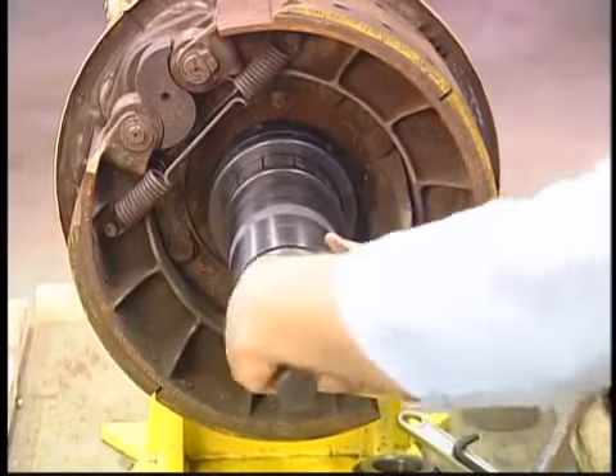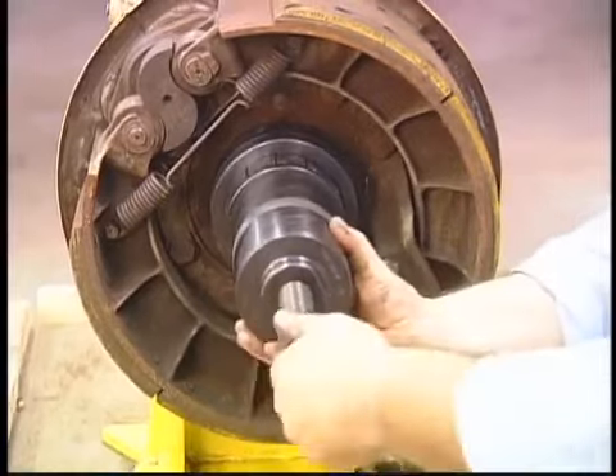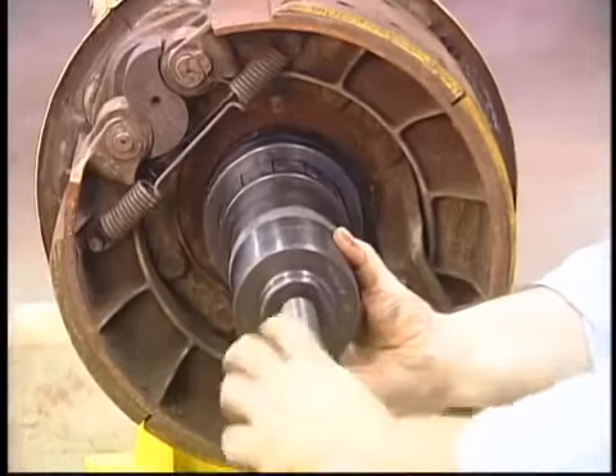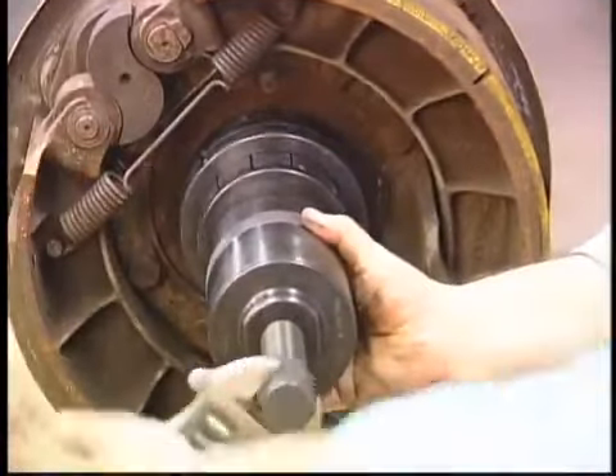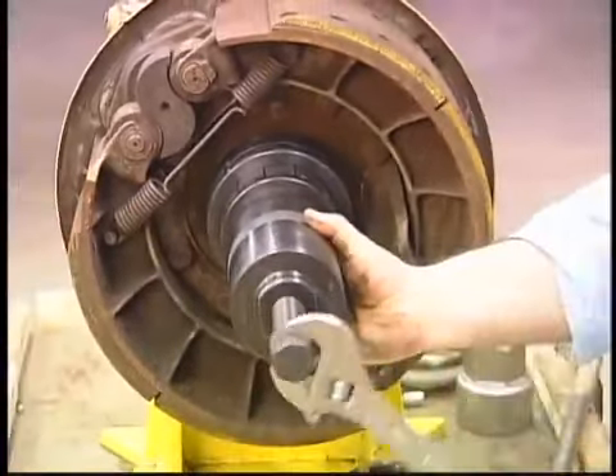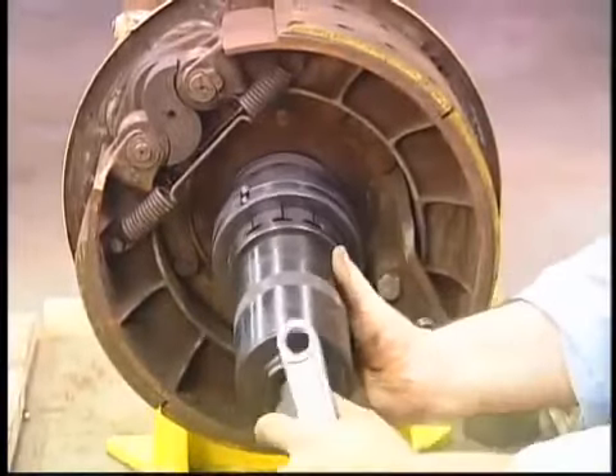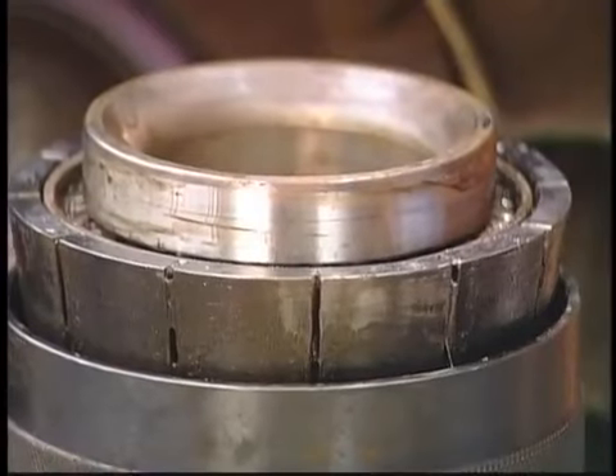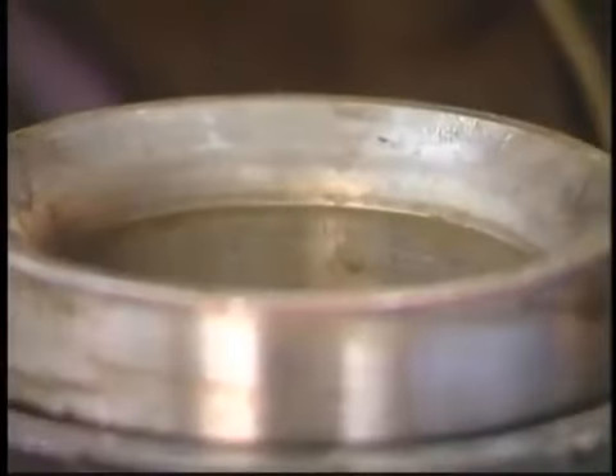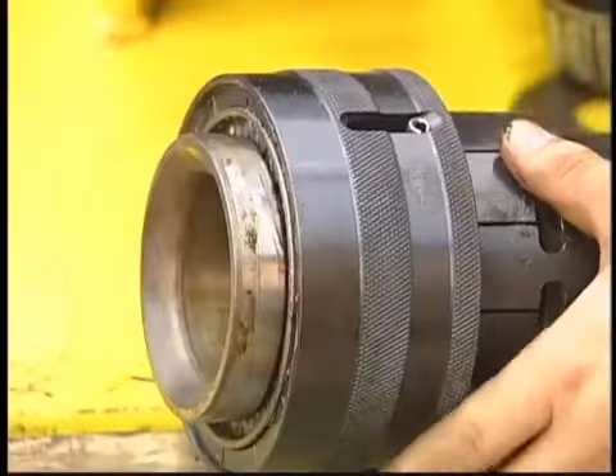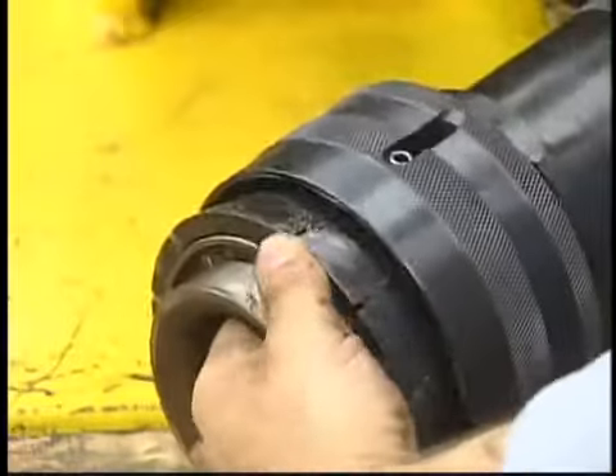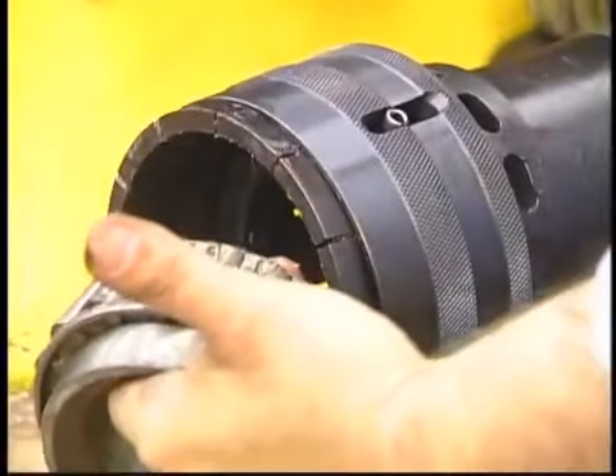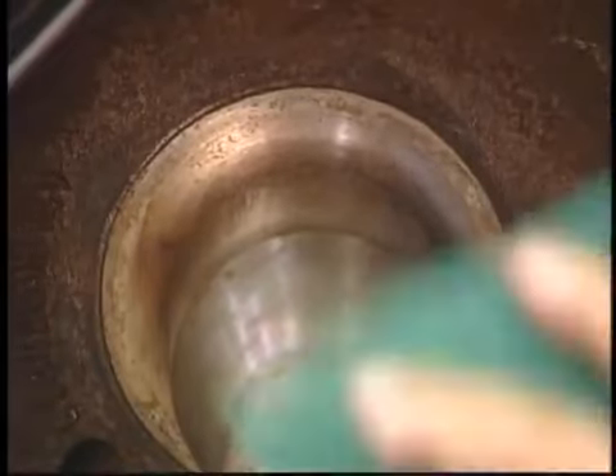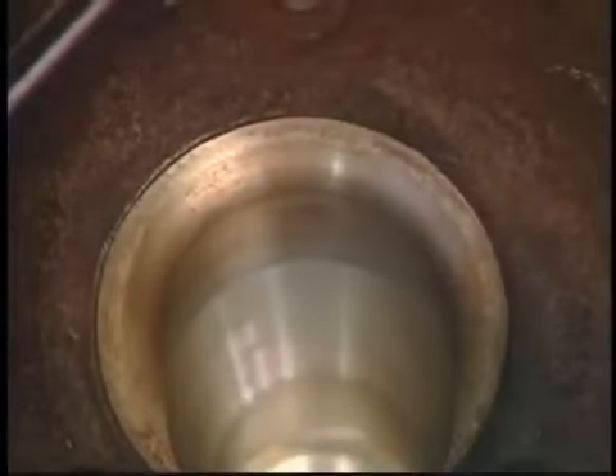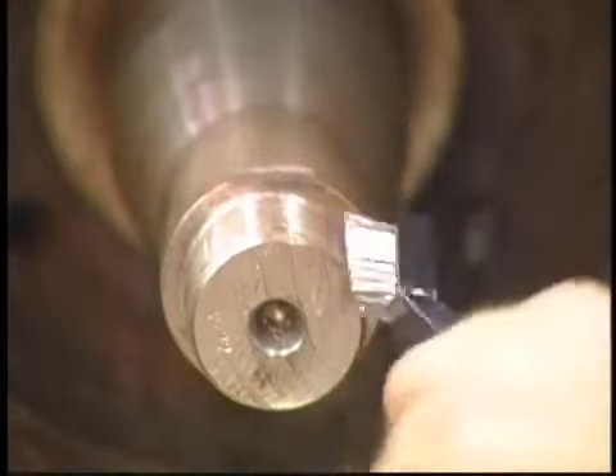Thread the forcing screw and its adapter into the collet. Tighten the forcing screw by hand to remove any slack. Use a wrench on the forcing screw to remove the bearing completely. Examine the seal wear surface for grooving. To remove the bearing from the collet, slide the sleeve back and gently tap the collet on a block of wood. Check the bearing for rust or pitting. The spindle may have some rust on it. Clean any rust with a Scotch-Brite pad or similar mild abrasive. Remove any dirt from the spindle threads with a soft wire brush.